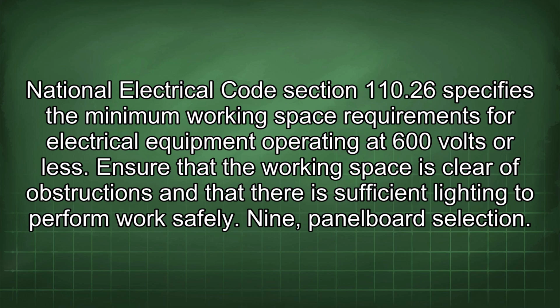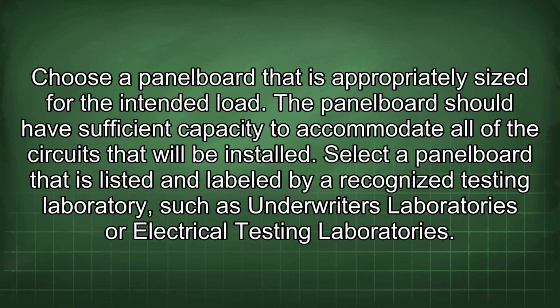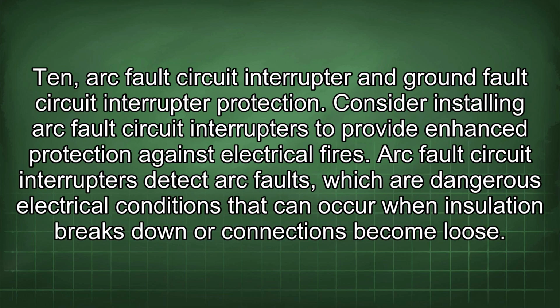9. Panel board selection. Choose a panel board that is appropriately sized for the intended load. The panel board should have sufficient capacity to accommodate all of the circuits that will be installed. Select a panel board that is listed and labeled by a recognized testing laboratory, such as Underwriters Laboratories or Electrical Testing Laboratories.